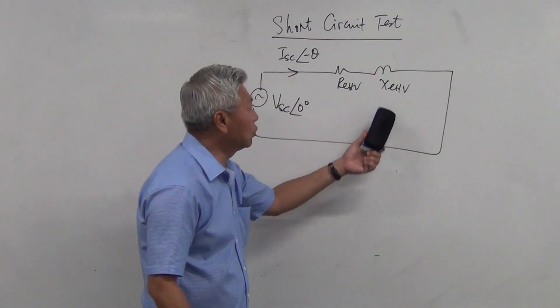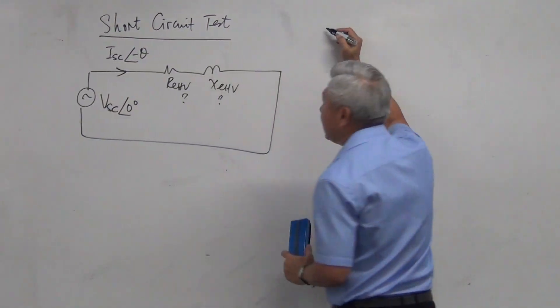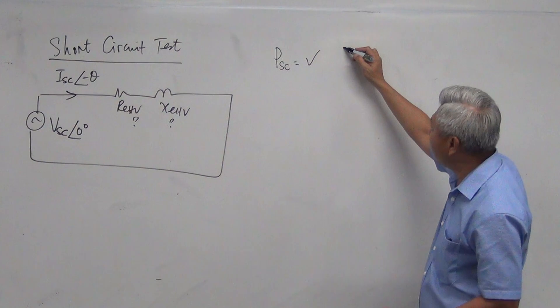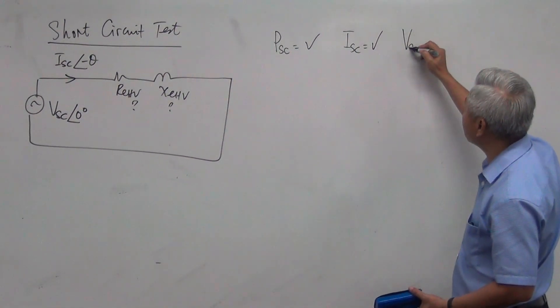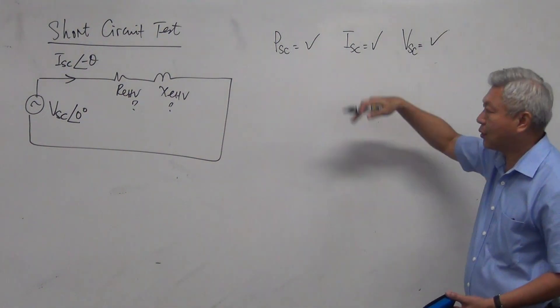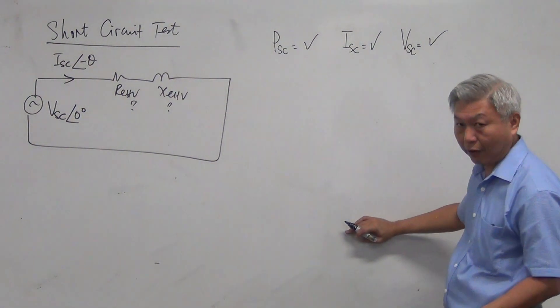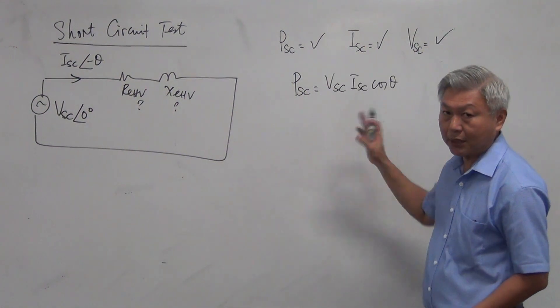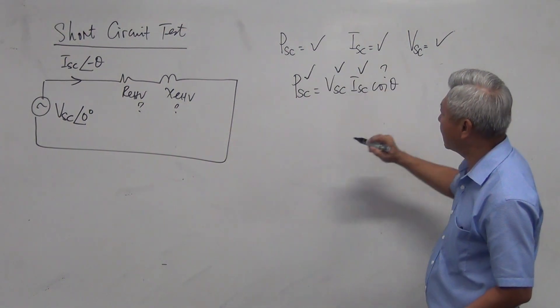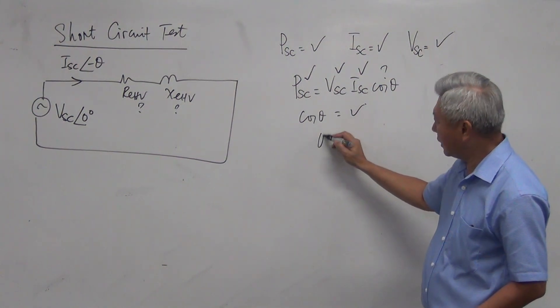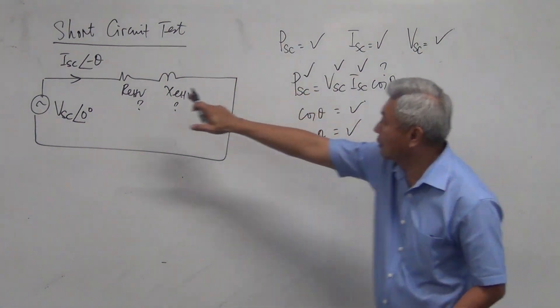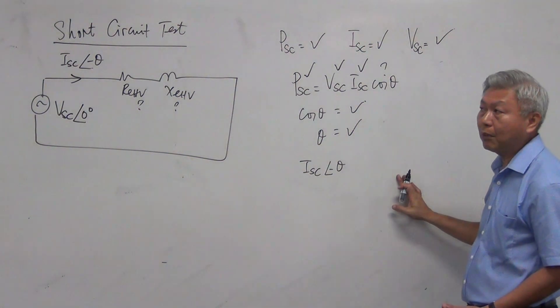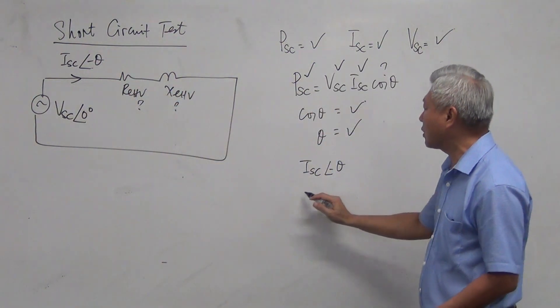Let us look at the mathematics and how to derive these two values. The three measuring instruments give us: the wattmeter to measure power PSC, the ammeter to measure short circuit current ISC, and the voltmeter to measure voltage VSC. We start with PSC = VSC × ISC × cos θ. You have PSC, VSC, and ISC, so cos θ can be found and then theta can be found by taking the inverse cosine.